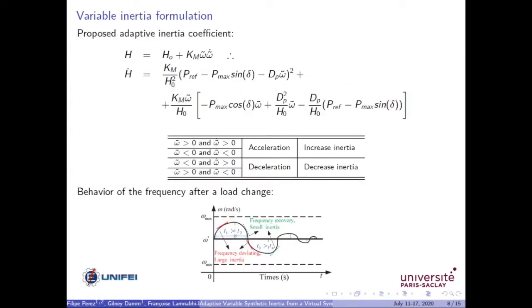Therefore, the derivative of the inertia coefficient is given as follows. The idea here is to vary the inertia in transients according to the system condition. We can see in the figure, when the frequency is increasing, a large inertia can reduce the frequency deviation. And when the frequency is recovering, going back to the equilibrium point, the small inertia can help to increase the speed of convergence.